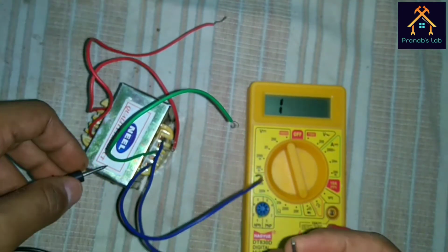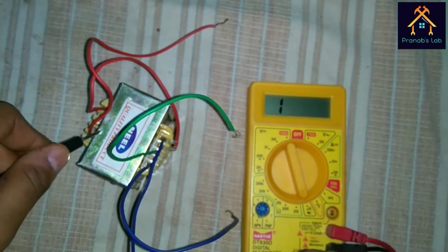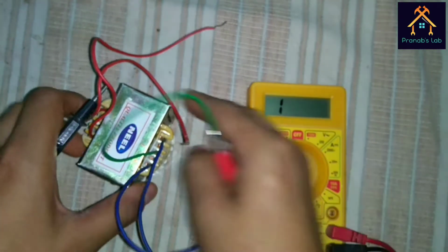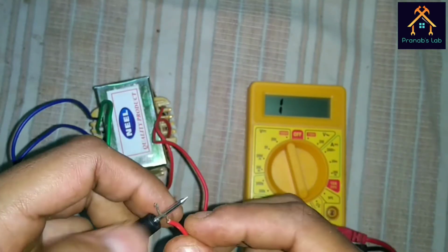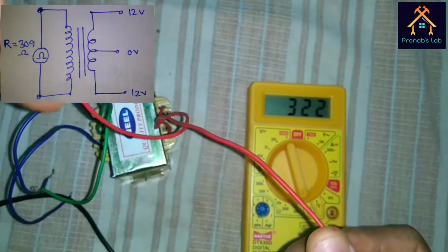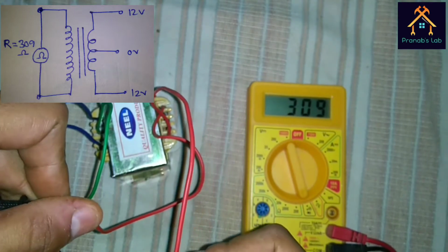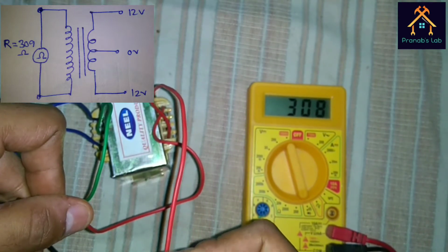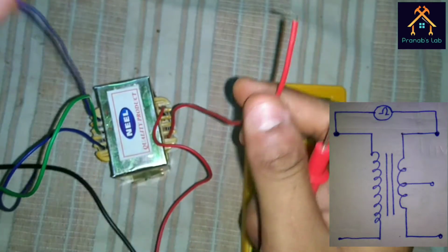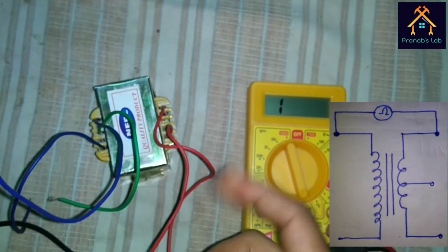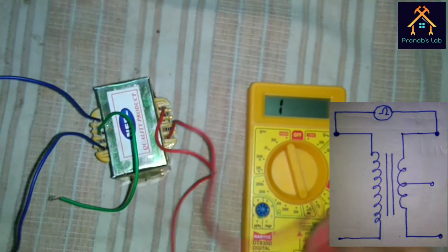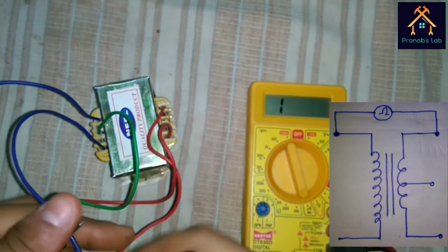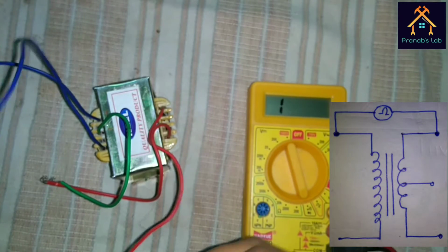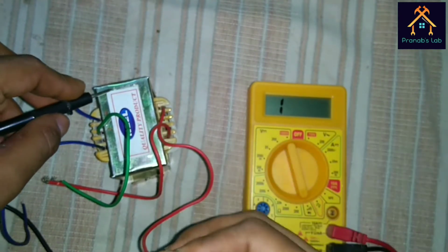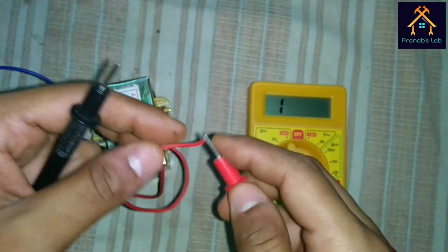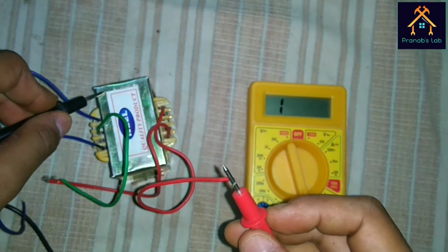Now the continuity of the cover is checked to see if any winding insulation is damaged. Now let's test the continuity of the high voltage winding, and we can't hear the beep noise because the resistance of the winding is high, that means 309 ohm. Let's test the continuity between the two windings. This 1 showing on the multimeter indicates that there is no electrical connection between the high voltage and low voltage windings. Now the continuity on the cover is checked as earlier to see if any winding insulation is damaged.